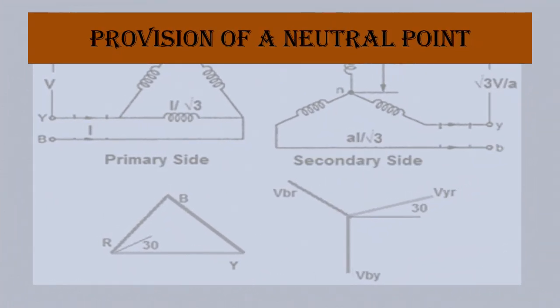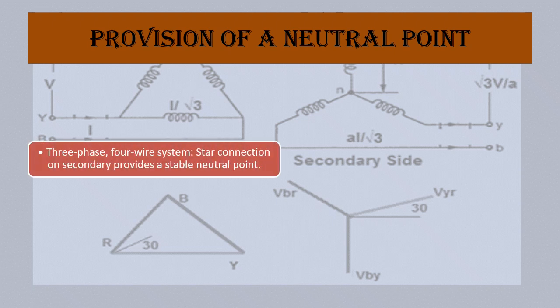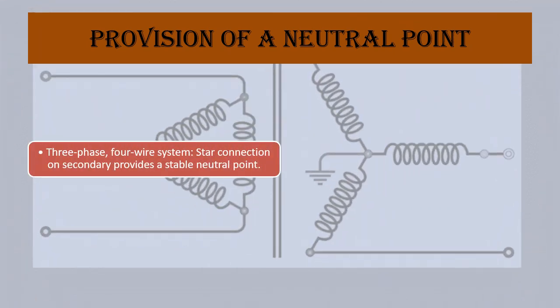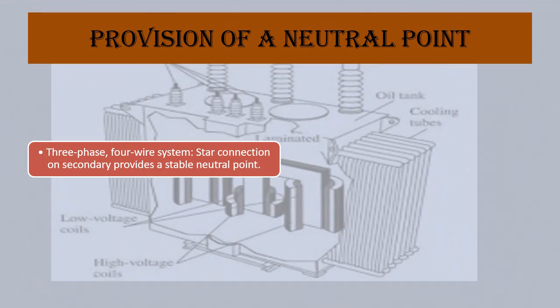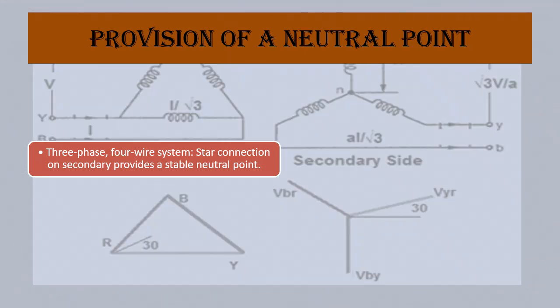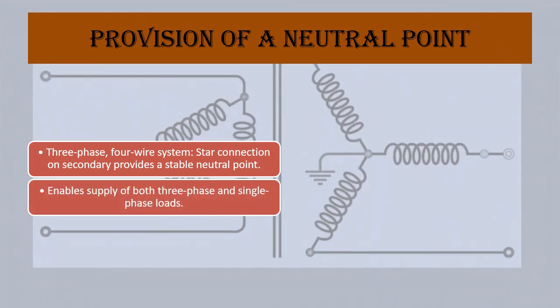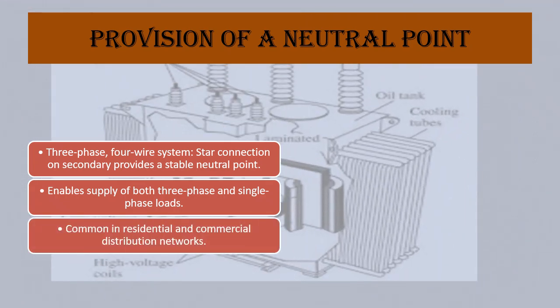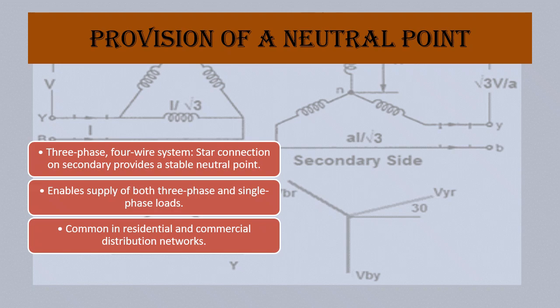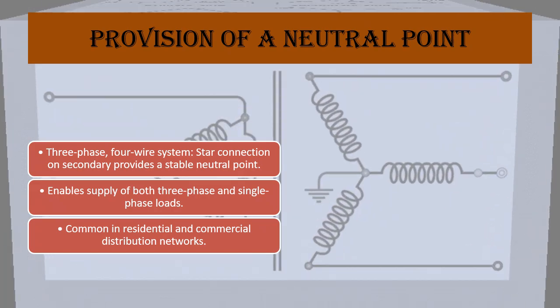One of the biggest advantages of Delta-Star transformers is the provision of a neutral point on the secondary side. This allows the system to supply both three-phase loads, like motors in industries, and single-phase loads, like appliances in homes. The ability to serve a mix of loads makes this configuration perfect for residential and commercial distribution networks.